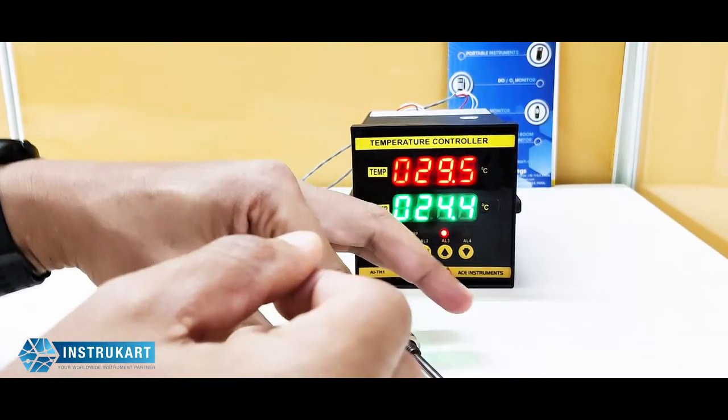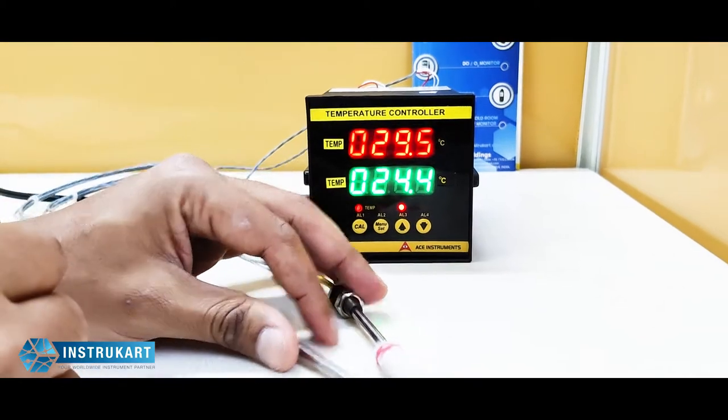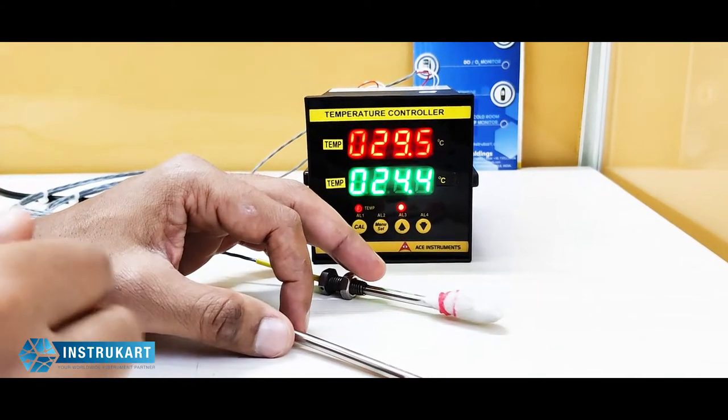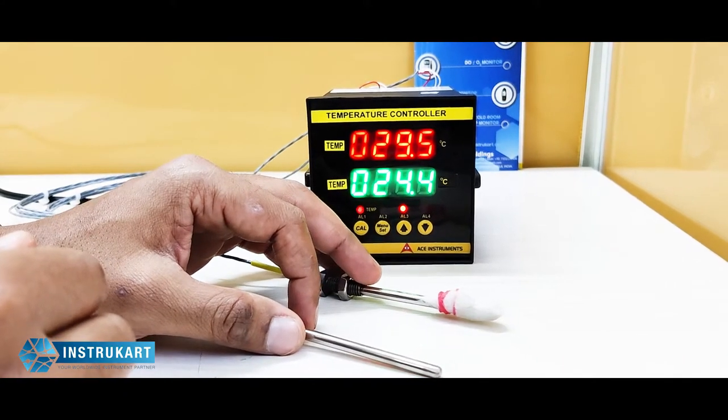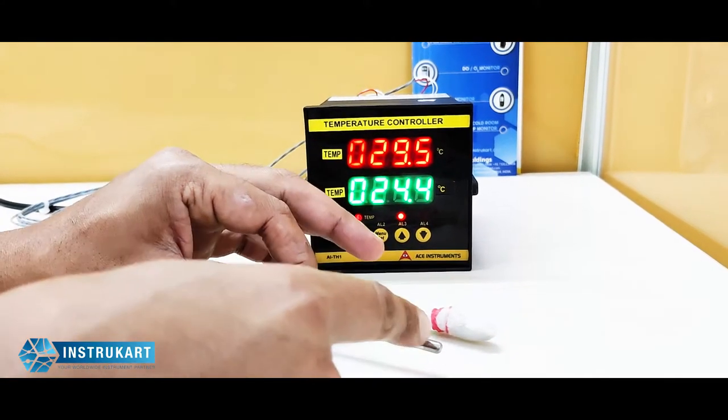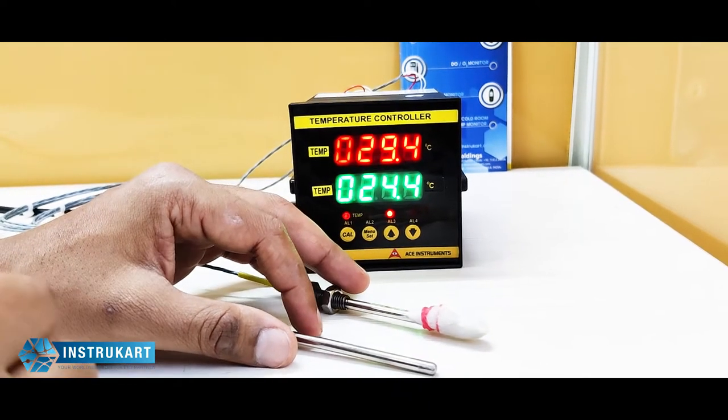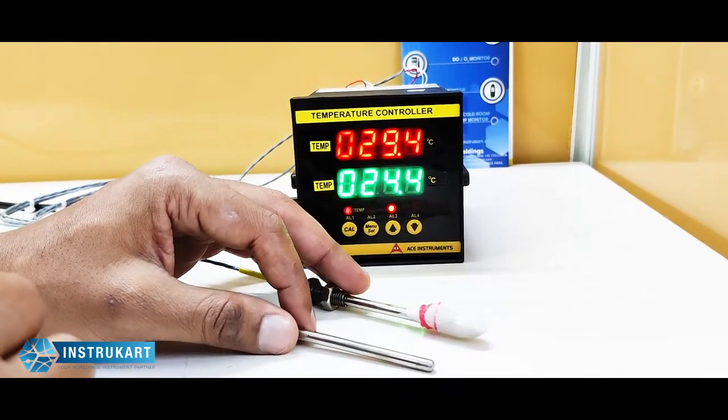The difference between the dry and the wet bulb is related to the relative humidity, which means that if the relative humidity is 100% in ambient, the dry bulb and the wet bulb will be the same. It means that there is no evaporation.